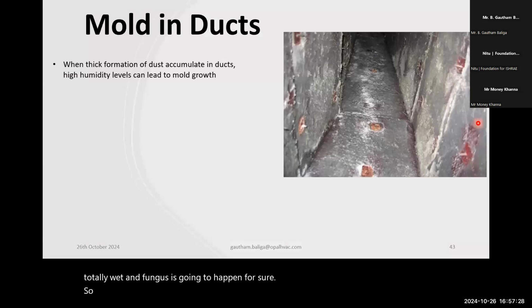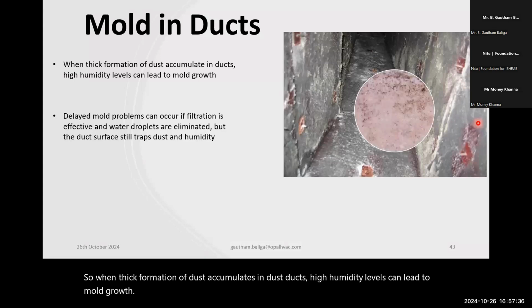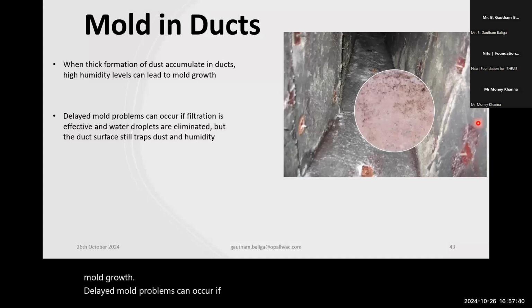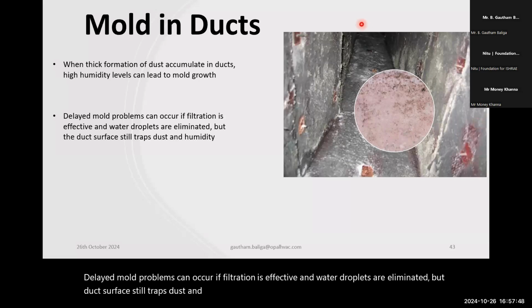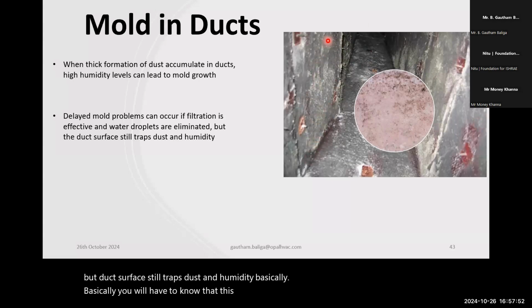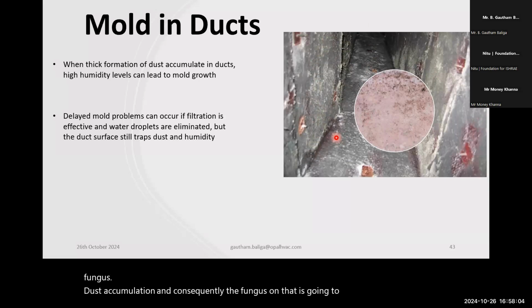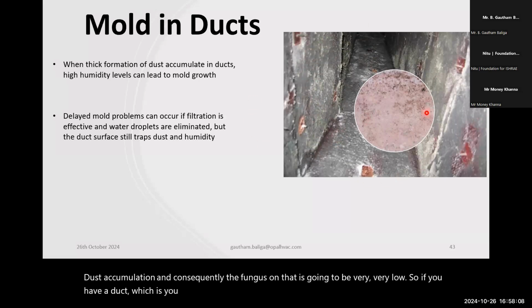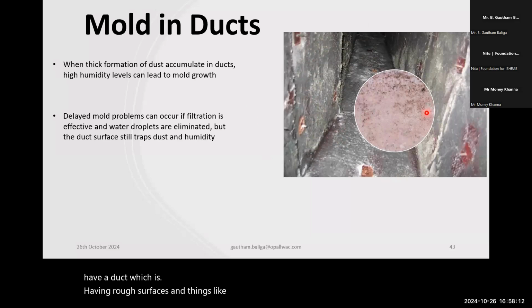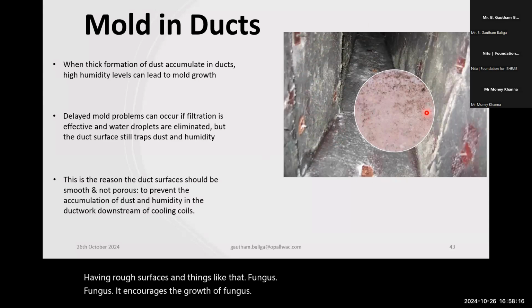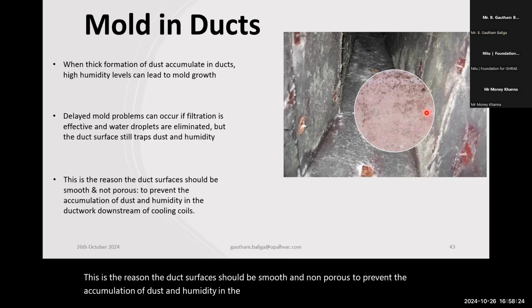So when a thick formation of dust accumulates in ducts, high humidity levels can lead to mold growth. Delayed mold problems can occur if filtration is effective and water droplets are eliminated, but the duct surface still traps dust and humidity. See, basically, you'll have to know that if this duct is very, very smooth from inside, the chance of dust accumulation, and consequently fungus on that, is going to be very, very low. If you have a duct which has rough surfaces and things like that, it encourages the growth of fungus. This is the reason the duct surfaces should be smooth and non-porous to prevent the accumulation of dust and humidity in the ductwork downstream of the cooling coils.